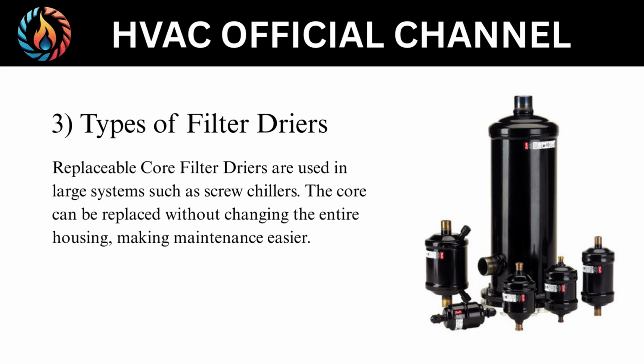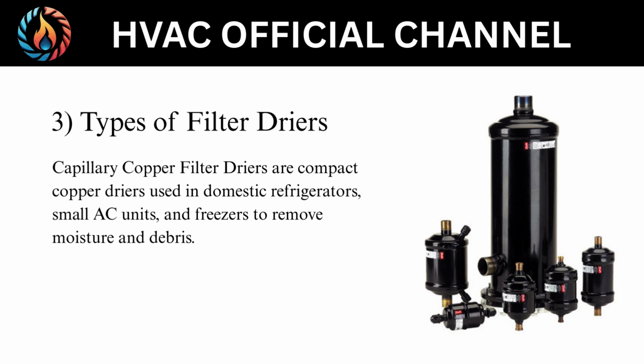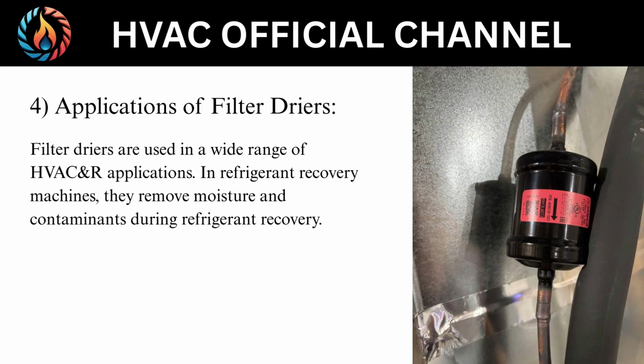Replaceable core filter dryers are used in large systems such as screw chillers. The core can be replaced without changing the entire housing, making maintenance easier. Capillary copper filter dryers are compact copper dryers used in domestic refrigerators, small AC units, and freezers to remove moisture and debris. 4. Applications of filter dryers.